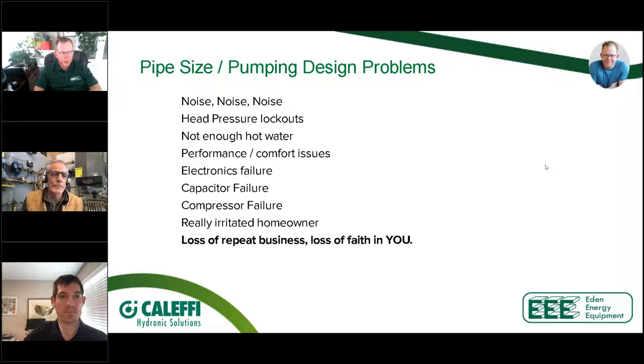If I can hear your heat pump running, I've got concerns about it. The other side effect is if we've got noise, then you're next going to tell me, hey Bob, I don't know what's going on with my heat pump, but it's really loud and it keeps starting and stopping. Well, that's you tripping the unit on head pressure, right? It's not delivering the BTUs. It's constipated, the unit. So we're knocking it off on head pressure.